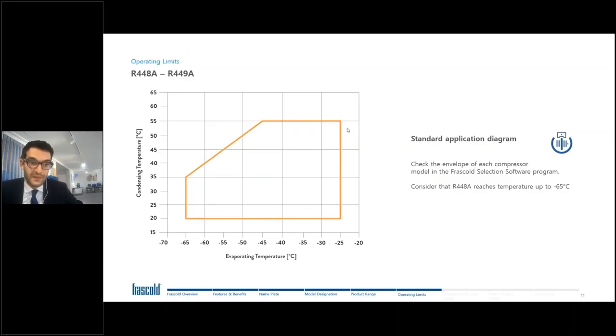Here we have the operating limits with 448A and 449A. It can work with evaporating temperatures down to -65 degrees, so it's clear that a standard single stage compressor arrives only down to -35, -40. That's why I said that these compressors are dedicated to applications where you really need to go low. We can talk about cryogenic segments, applications, or other industrial processes also, where you really need to go deep, in blast freezers and very, very low temperature freezers.